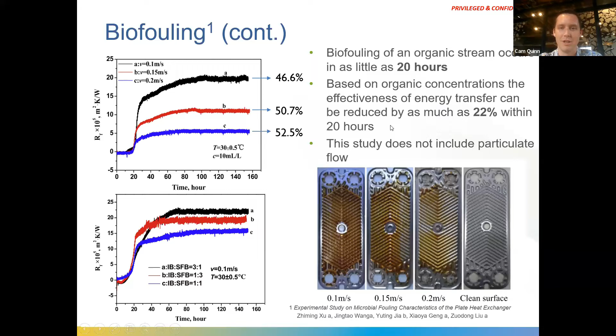Down here we just show some pictures of a clean surface, and then this showing how the biofilm grows on the plates in a plate frame exchanger. Biofouling can occur in as little as 20 hours and can reduce heat transfer effectiveness by as much as 22% within that time. This is a big challenge that needs to be overcome.